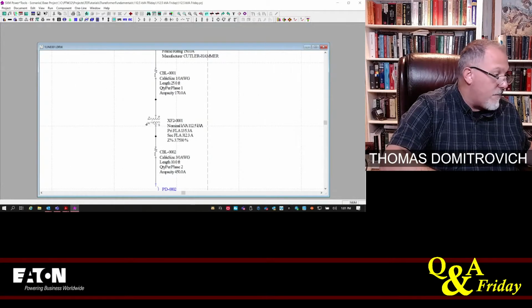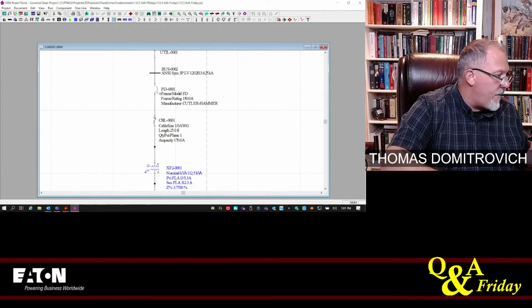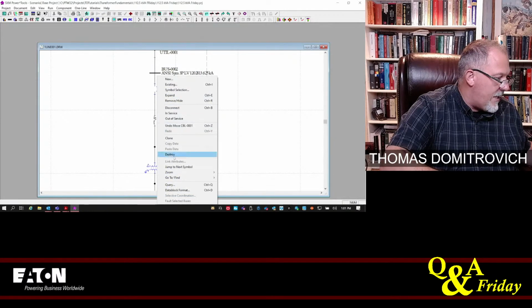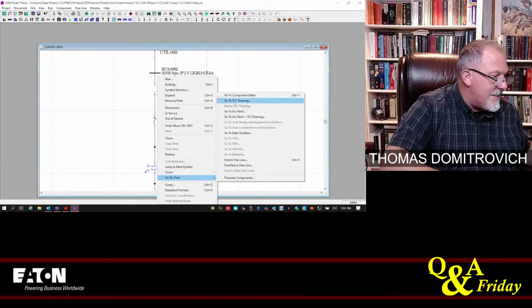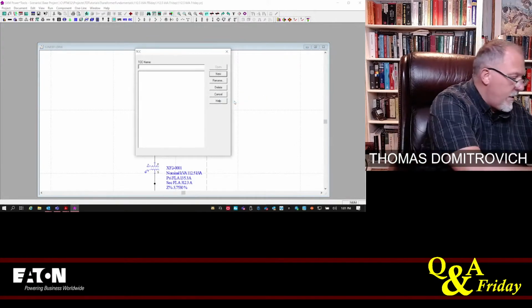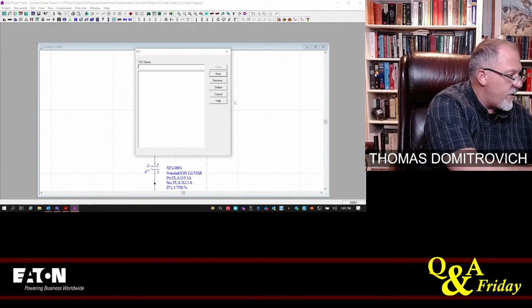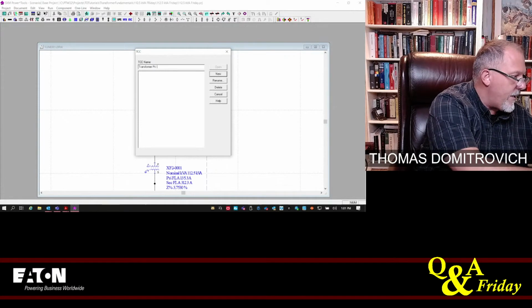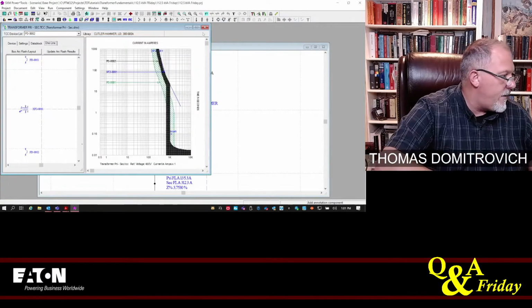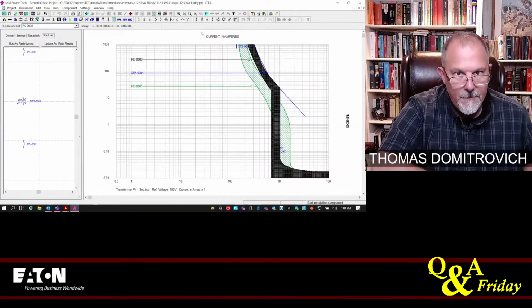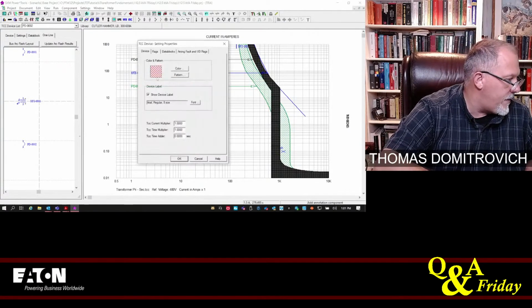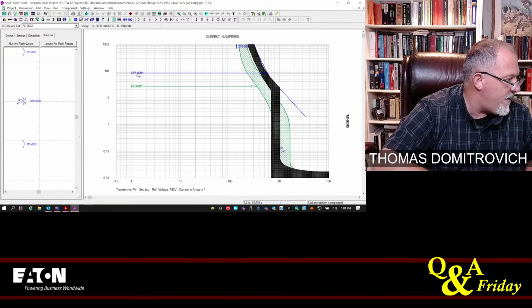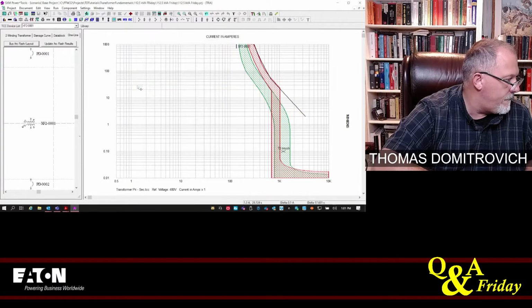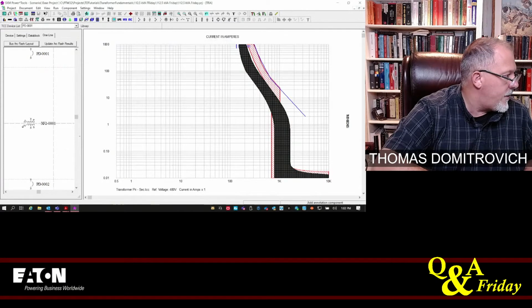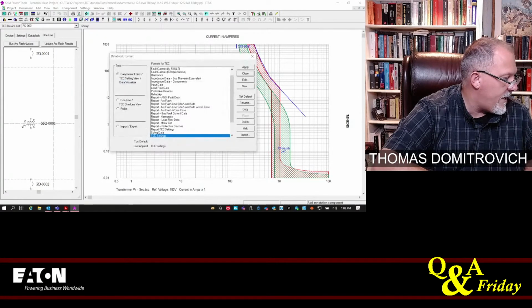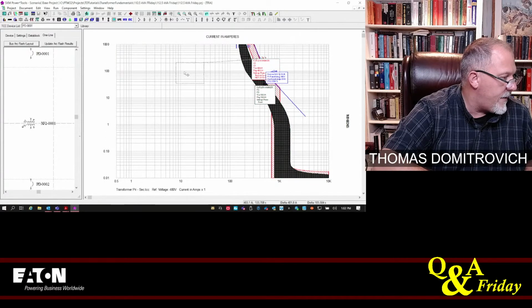I'm going to pick my transformer. And I'm going to pick my primary breaker. And I'm going to say, go to TCC. And we'll do transformer protection. Transformer primary, secondary. All right, there we go. So we got curves. Here is what I do. I do show label. I turn all of that off. And I go run data block format. I have TCC close. And that gives me the names.